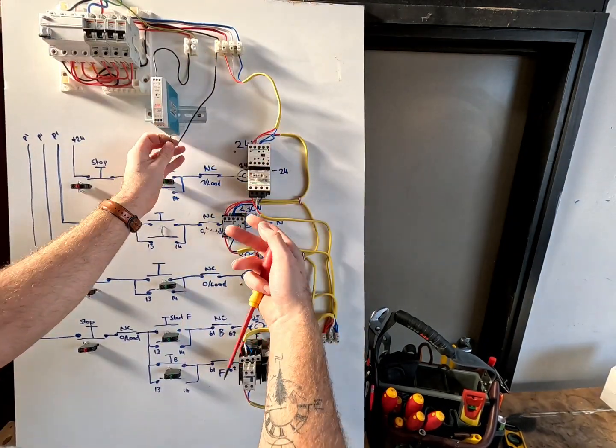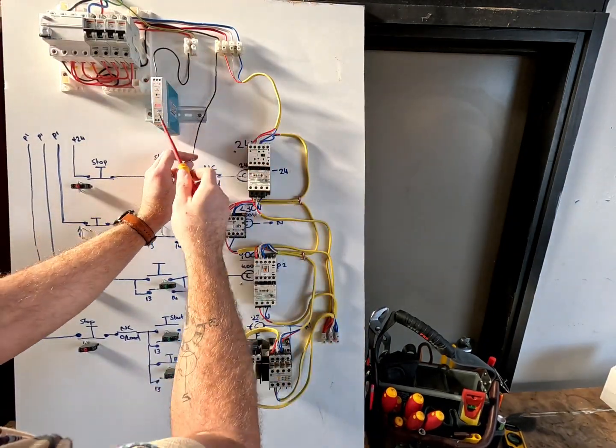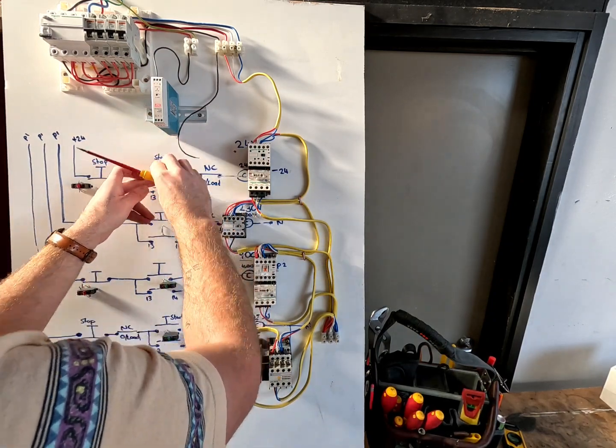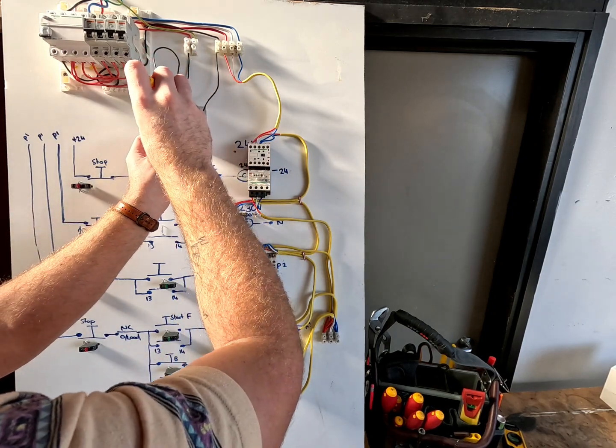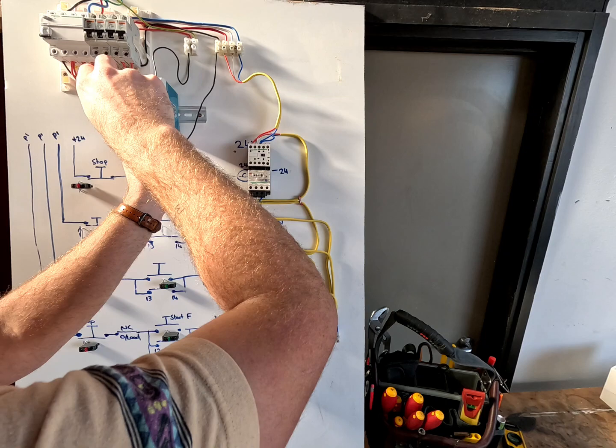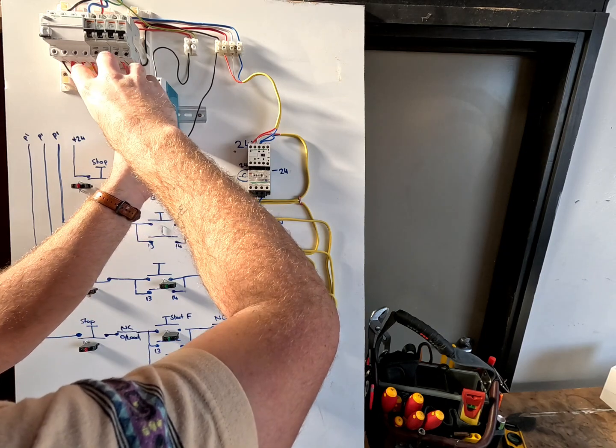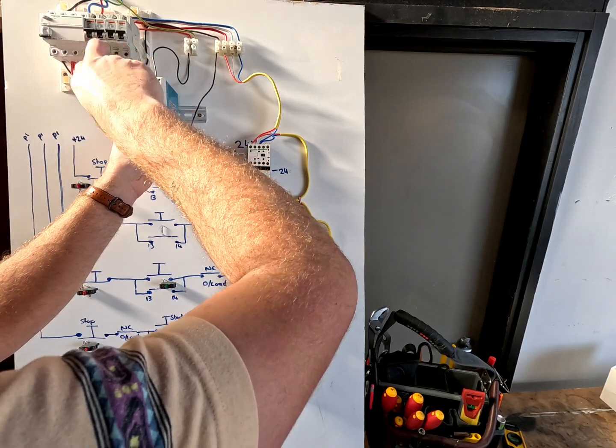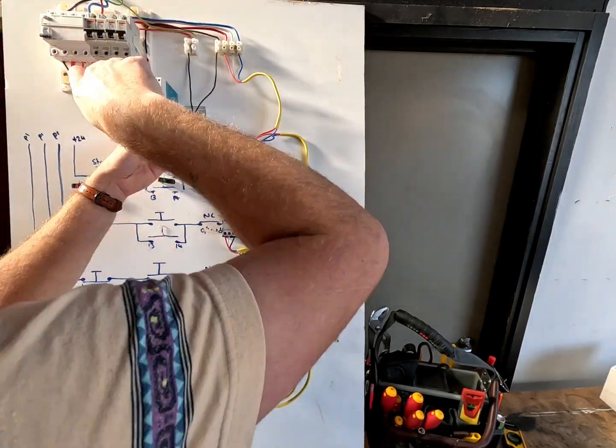So it really pays when you're doing this kind of thing to double check your terminations and whatnot. Just realized that I just put the live and neutral into the wrong end. Some transformers if you do that you will stuff them. So always pays to double check before you liven things. There you go.